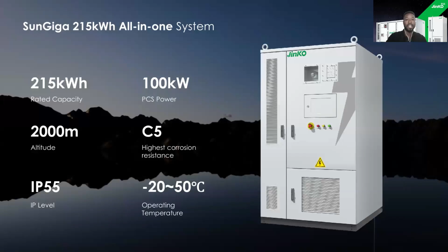So to kick things off, this is our current version, the G1 SunGiga. So this is a 215 kilowatt hour all-in-one system. It has an inbuilt PCS, which you can see on the bottom right-hand side, that door there with the grids. And that's where the PCS sits, and that's a 100 kilowatt PCS. It's inbuilt, so you're not having to add on an external PCS, taking up more space in applications where space might be limited. Yeah, as I said, it's 215 kilowatt hours, which is kind of a sweet spot for C&I.